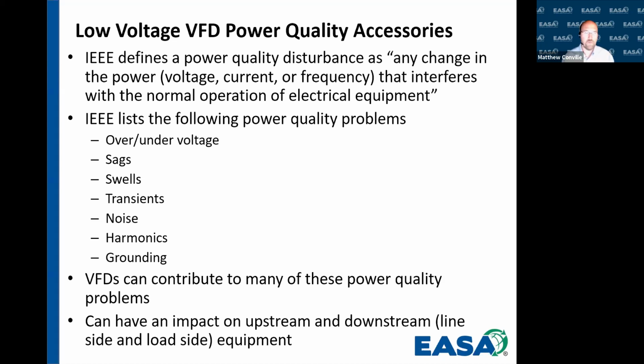Drives create power quality issues, or as IEEE calls them, disturbances. They define a disturbance as any change in the power, which is the voltage, current, or frequency, that interferes with the normal operation of electrical equipment. IEEE lists some of the following power quality problems that need to be looked at: over voltage or under voltage, sags, swells, transients, noise, harmonics, and grounding. Nowhere in here will you see the term spike used. They're very particular in their naming. They don't want it to be ambiguous. So for us, spikes are typically going to be in the form of grounding, harmonics, and transients, and sometimes noise. So it's really important that we delineate what these are.